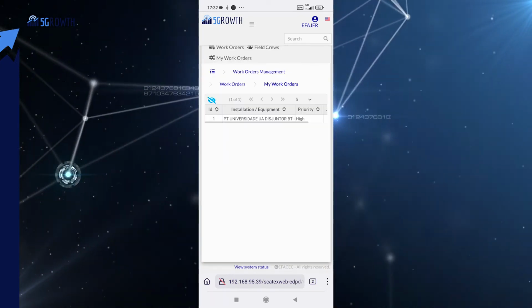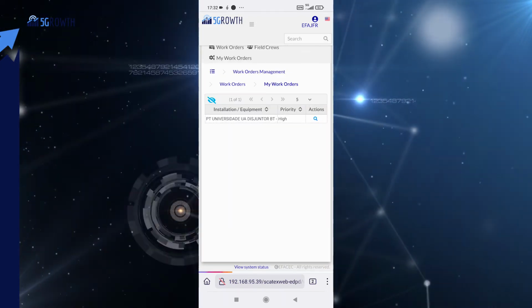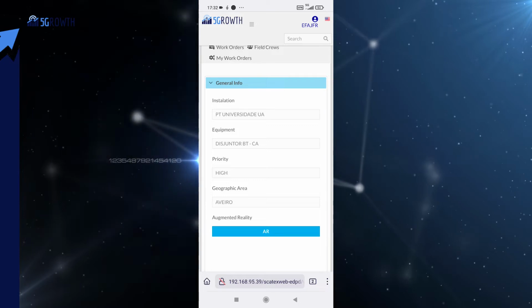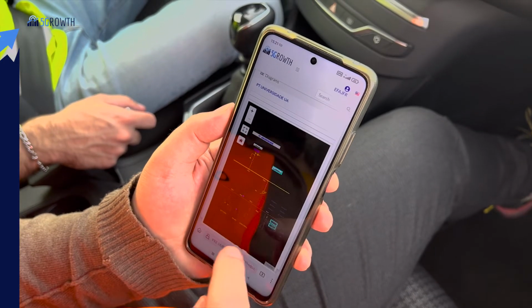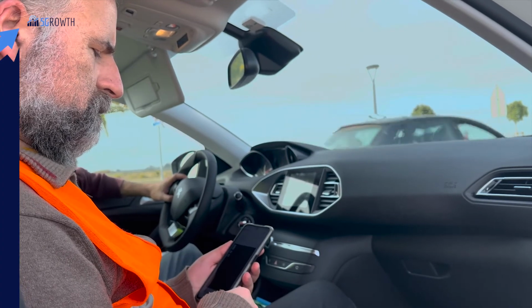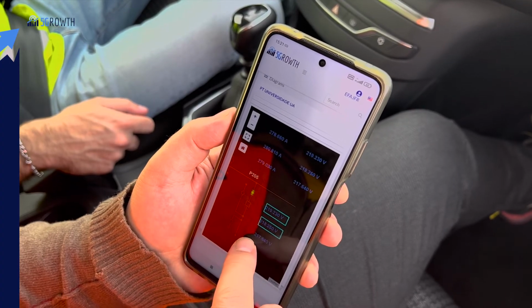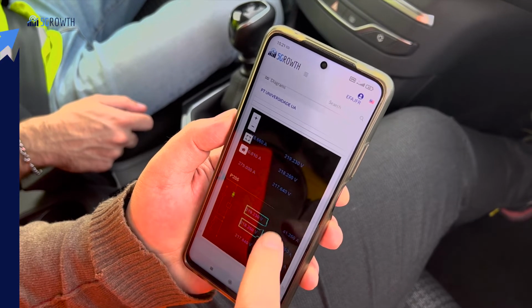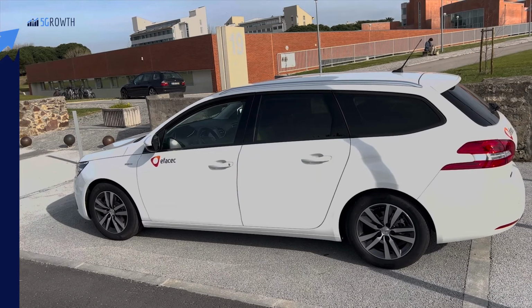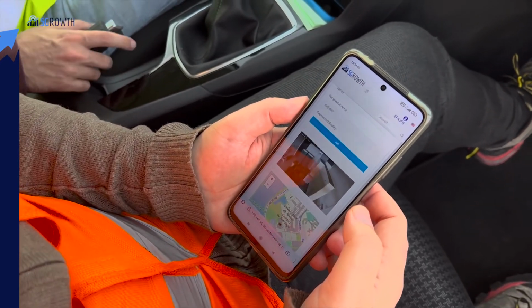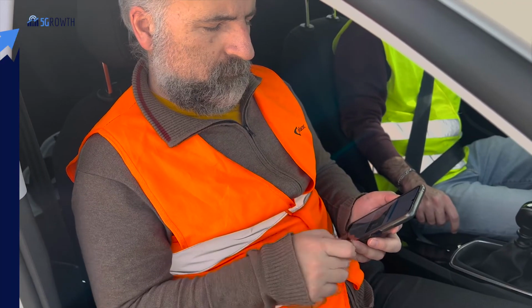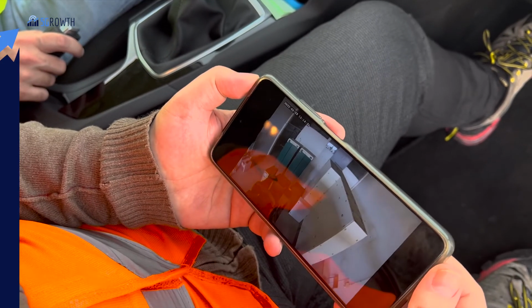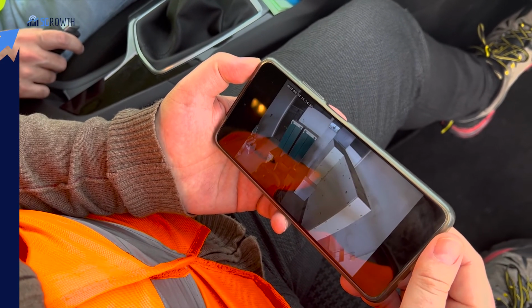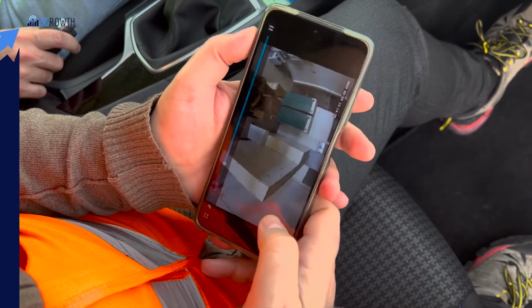Meanwhile, an incident ticket will be issued and assigned to a nearby field crew to investigate the fault event. The field crew has immediate access to the work order related to the incident using a 5G mobile device connected to the 5G network. With the mobile interface, the field crew can get real-time information from the secondary substation, such as the telemetry, the alarms, and the live video feed from inside the substation. This information helps the field crew to assess the fault in advance and better prepare to solve it.